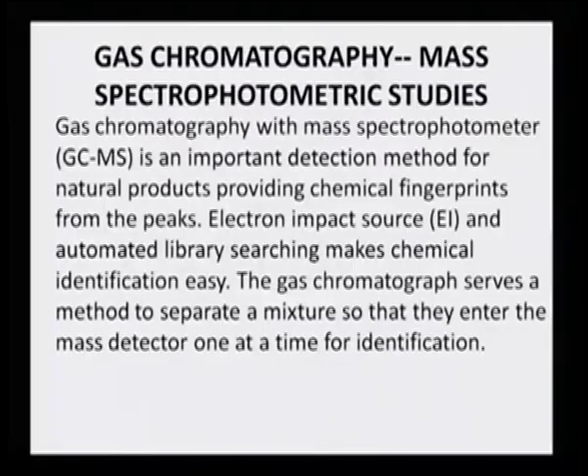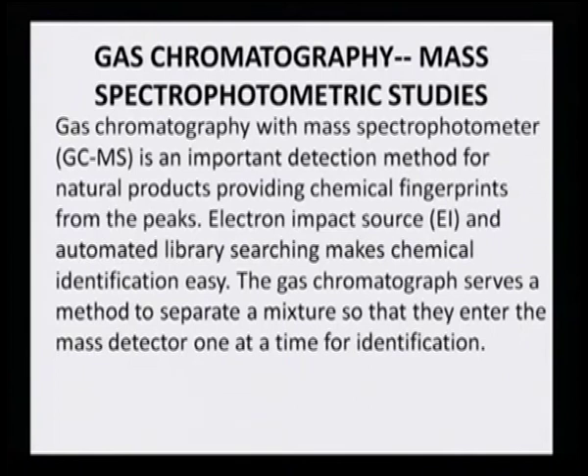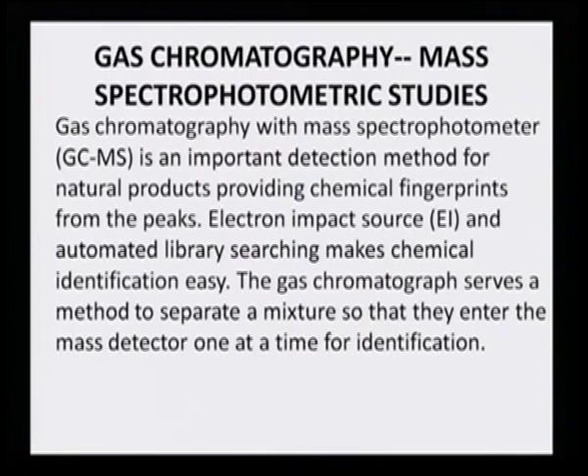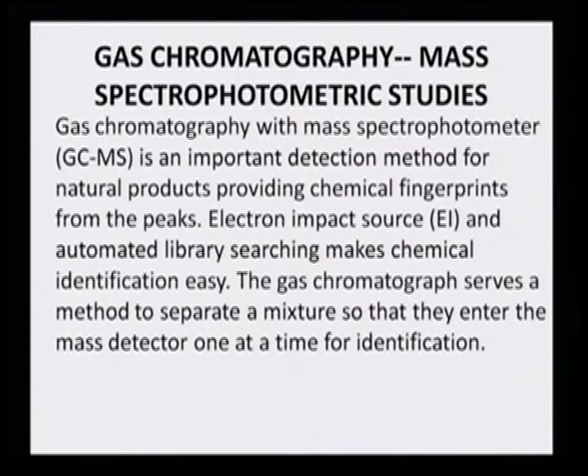Gas chromatography can be used alone or combined with mass spectrometric studies. GC-MS is an important detection method for natural products, providing chemical fingerprints. Electron impact source (EI) and automated library searching makes chemical identification very easy. The gas chromatography serves to separate a mixture so that components enter the mass detector one at a time for identification — the chromatography separates them and the mass detector then detects them, finding out whether the fragmentation pattern matches a known or unknown compound using library research.